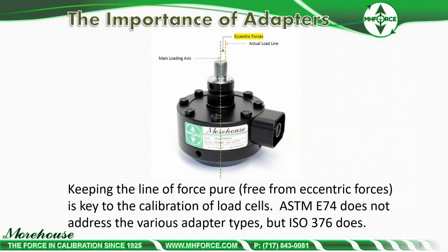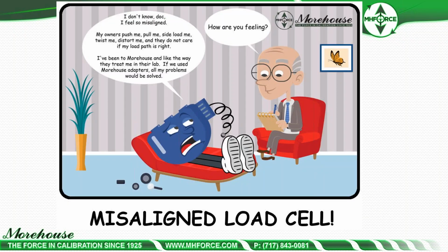So when we start talking about the importance of adapters, we're talking about keeping the line of force pure, free from eccentric forces, and it's the key to calibration of load cells. ASTM E74 does not address it, but ISO 376 does. They talk about the adapters needed to keep the line of force pure, and they give you recommendations in their annex. Just a really good document. Those that are calibrating to ISO 7500 should know ISO 376 quite well, because that is the standard you need to have to perform calibrations in accordance with 7500.